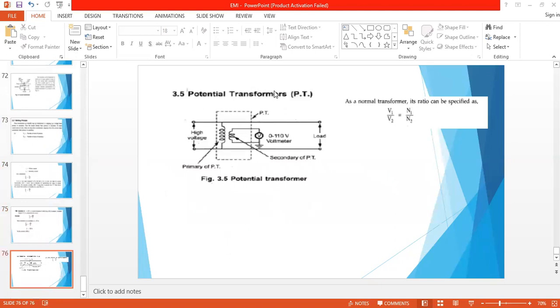Coming next to the potential transformer. It has a primary winding and secondary winding. The primary winding of the potential transformer is connected to high voltage, and the secondary winding is connected to a low-range voltmeter. It is a step-down transformer because the voltage is stepped down from high voltage to low voltage — for example, to a 110-volt meter. The primary winding has a large number of turns and the secondary winding has fewer turns, just like a normal transformer. The ratio is V1 by V2 equals N1 by N2.